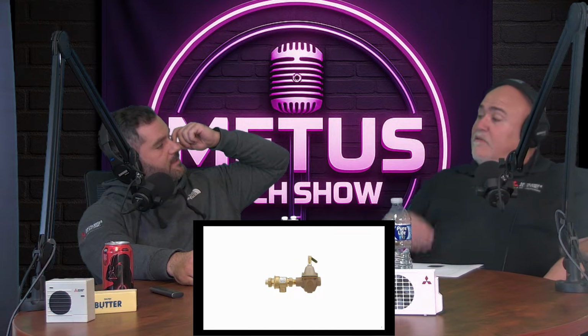Yeah. So that backflow preventer also has a connection on the bottom where you can pipe that down low. So in case it does start to leak, it can relieve that water somewhere. Yeah, believe it or not, a lot of the valves or relief valves that we have, whether it's the backflow preventer or even the pressure relief valve, it's just an open port that you can do whatever you want with.